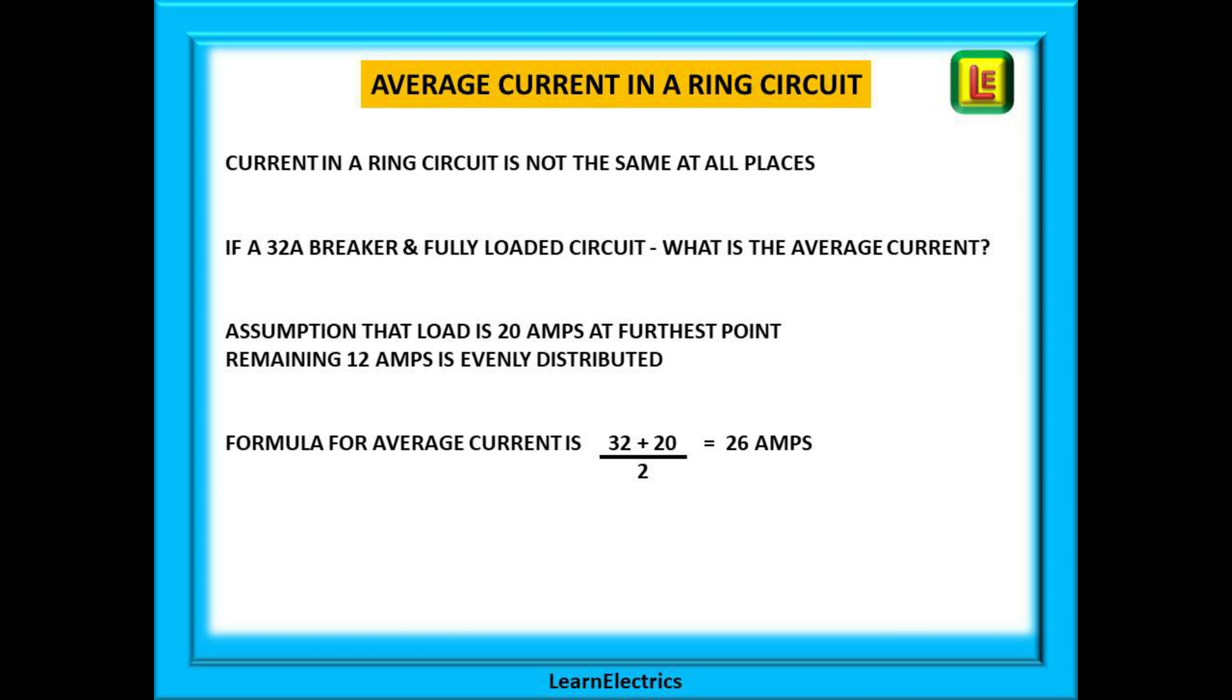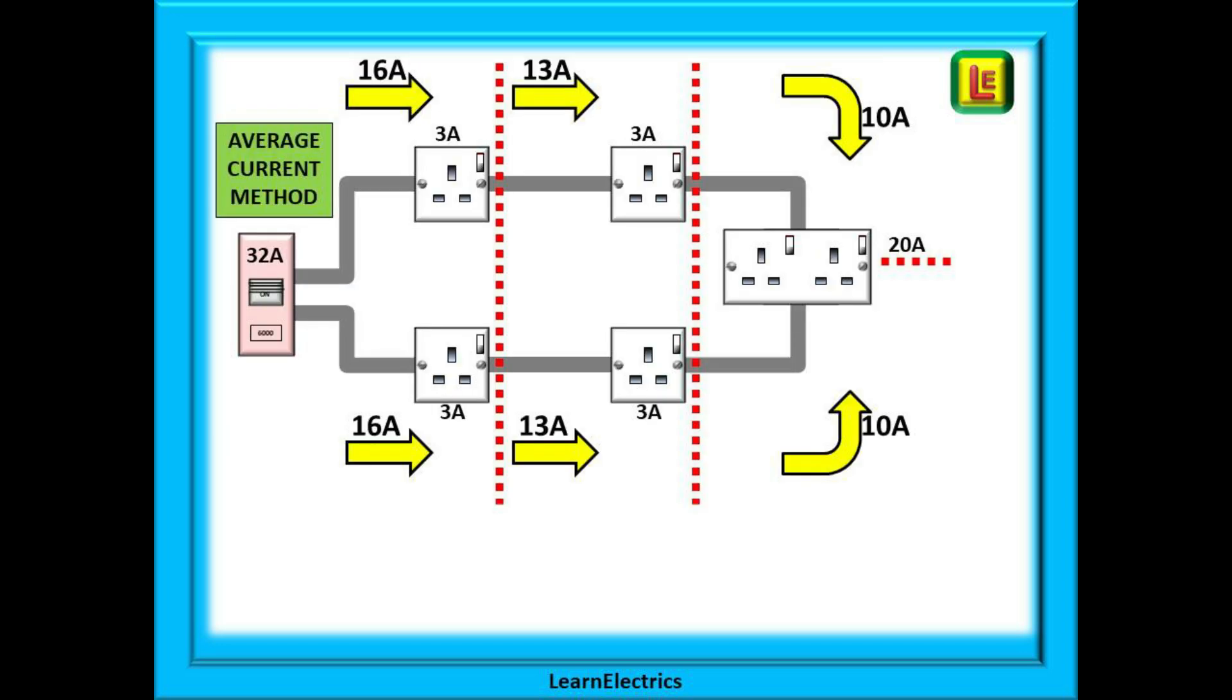The full load current plus the current demand at the furthest point are added together and then divided by 2. This gives us 32 plus 20 which is 52, divide 52 by 2 and we have our average current of 26 amps.